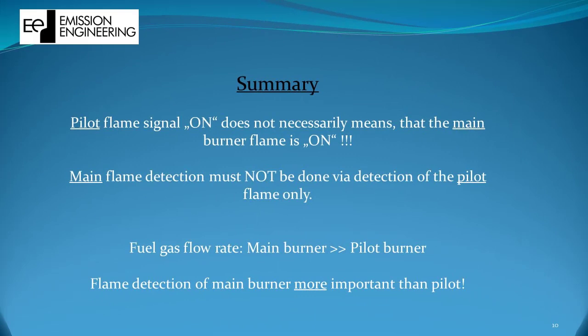Let's summarize. A pilot flame is on does not necessarily mean that the main burner flame is on. The correct conclusion that one should take from there is that a main flame detection must not be done via detection of the pilot flame.